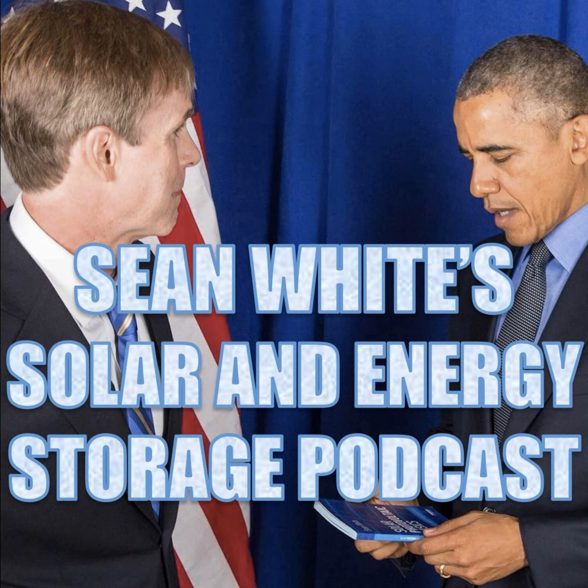And so we said, okay, we have to have something that controls this stuff, because the reality is Article 705.12, which talks about load side connections, is all written around the fact that we have no control over this stuff. It's just crazy. Throw solar power at buildings, and you got to do it right. What if, crazy stuff, we actually measured how much power is coming from the grid, and we measured how much power is going to a panel, and then we had some brains that said, you know what, we need this much power, so let's do that.